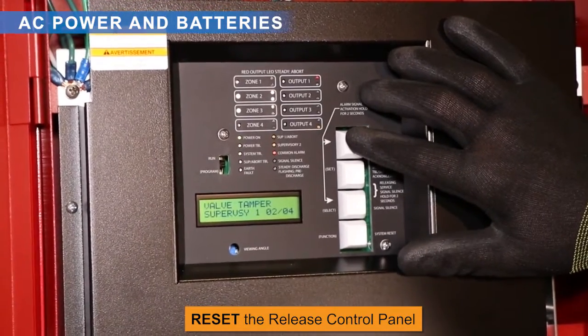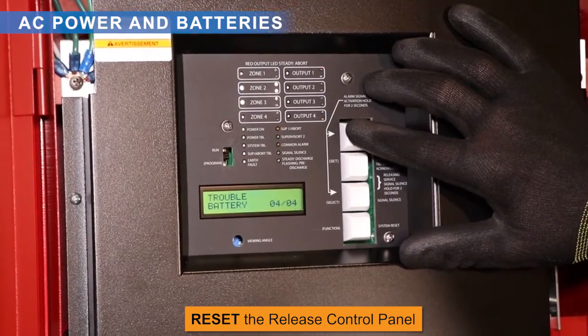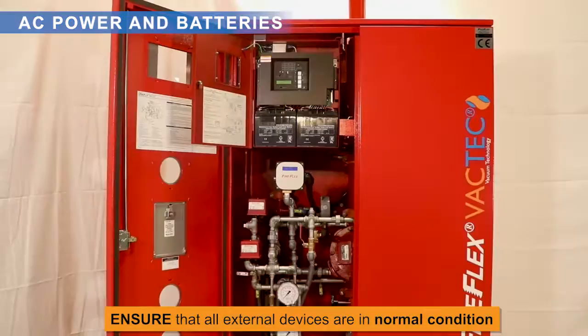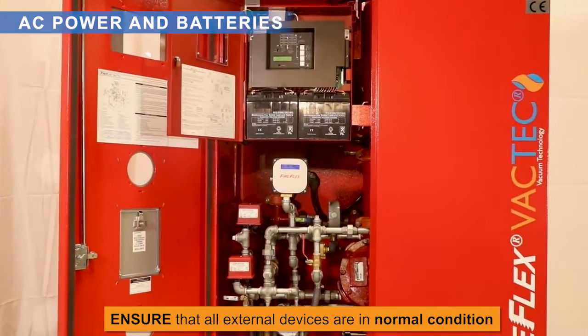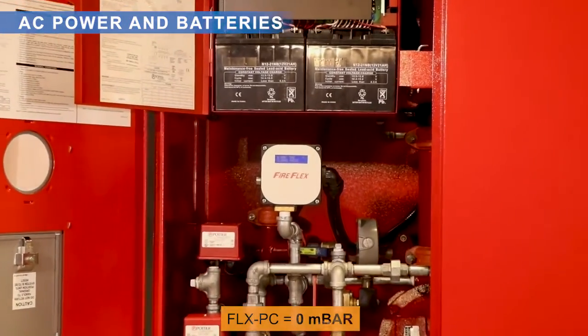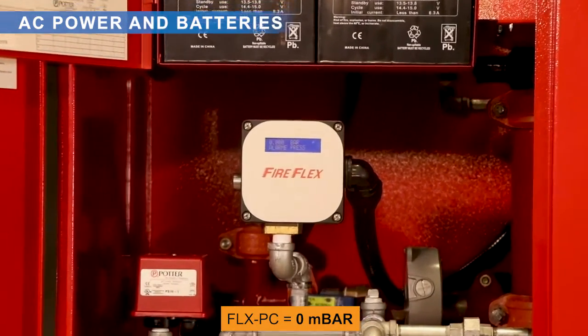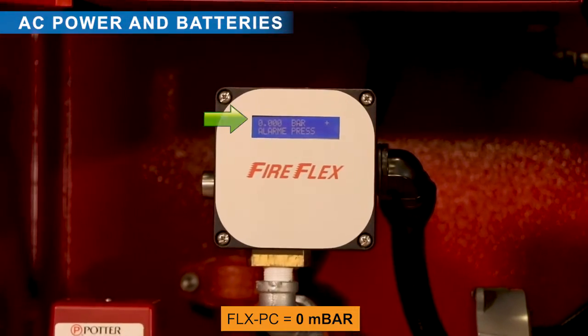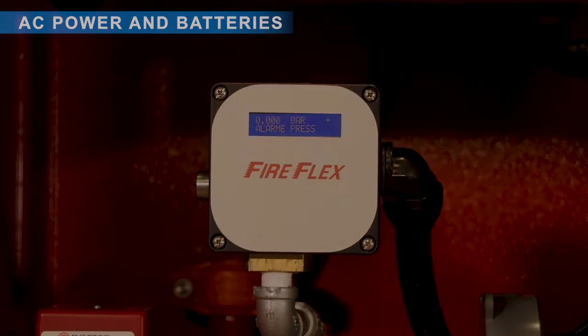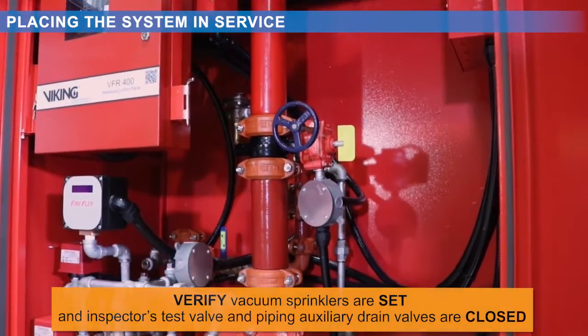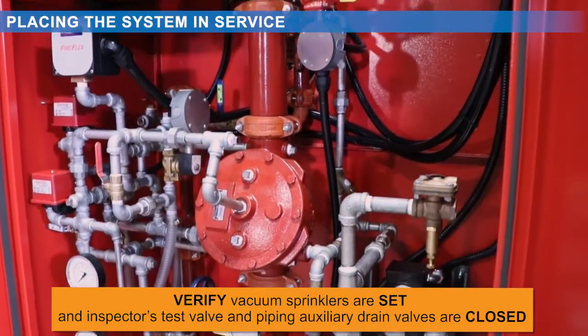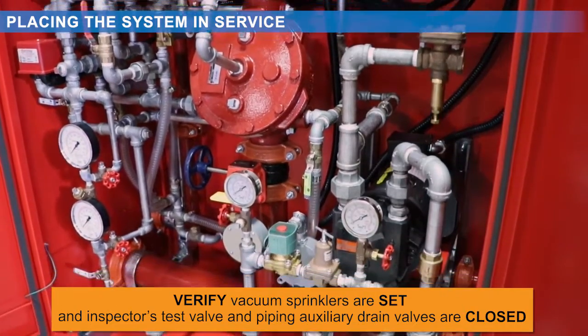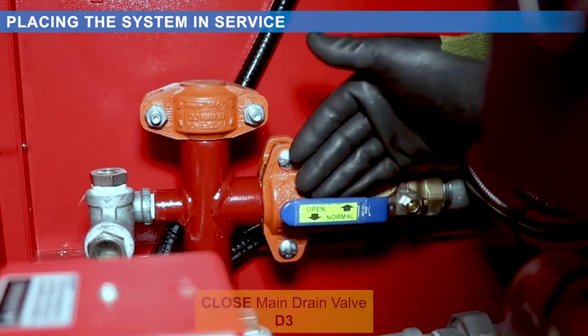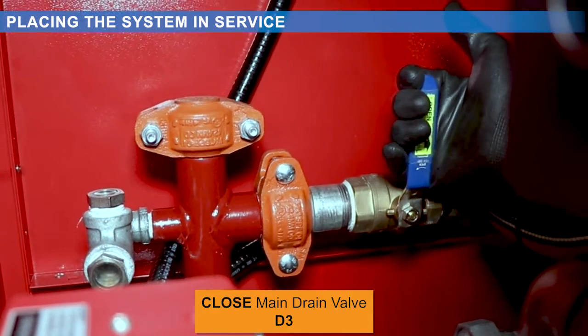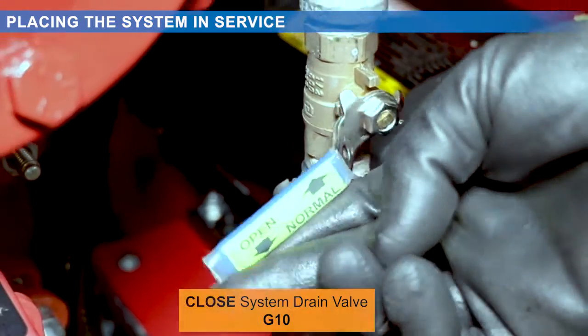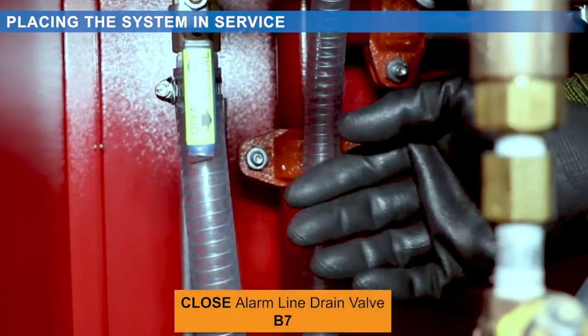Reset the release control panel and acknowledge all conditions using the buzzer silence key. Ensure that all external devices are in their normal condition before proceeding. The vacuum pressure controller, FLX PC, should show 0 millibar. Verify that all vacuum sprinklers are set and that inspector's test valve and piping auxiliary drain valves are closed. Close main drain valve, system drain valve, and alarm line drain valve.